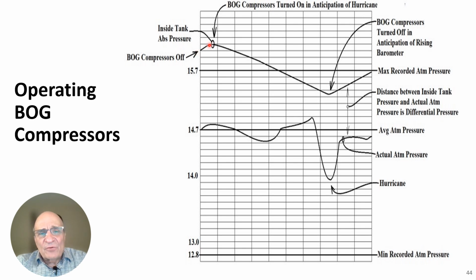So you as an operator, or as the engineer overseeing these operators, have to know your barometer projections for the next few days, increasing barometer, decreasing barometer, so that you can add some smarts to how you operate your boil-off compressors. And keep in mind, as you lower the tank pressure, your liquid is going to get colder and colder, which means it's going to boil off more rapidly. So it's not as easy as I'll just turn on the boil-off compressors and they'll bring the pressure down. As you bring the pressure down, it takes a significant period of time, because as you're dragging the pressure down, more boil-off is being generated.